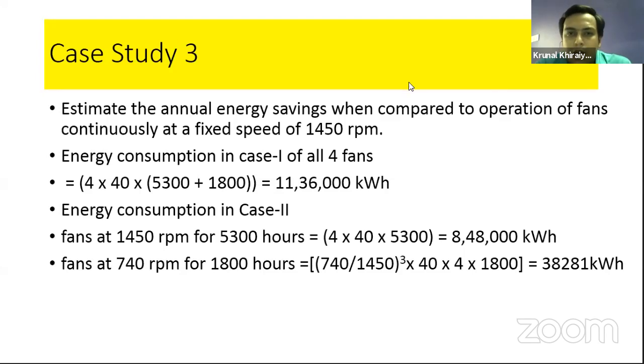Yes, the specific speed of the fan is linearly proportional to the power 3. Means P1 by P2 equals N1 by N2 to the power 3. That is the characteristic law of the fan.